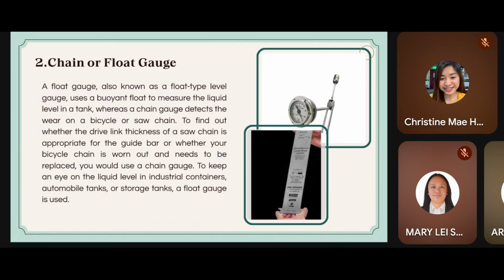For the chain or float gauge, it means it's a level measurement that is rivaled in simplicity and dependability by float-type measurement devices. Many forms of float-type instruments are available, but each uses the principle of a buoyant element that floats on the surface of the liquid and changes position as the liquid level rises. Many methods have been used to give an indication of level from a float position, with the most common being a float-and-cable arrangement. The operational concept of a float-and-cable is shown in the following diagram.